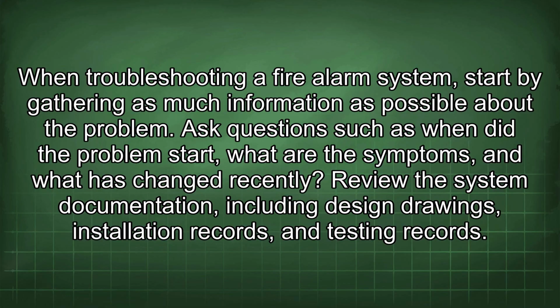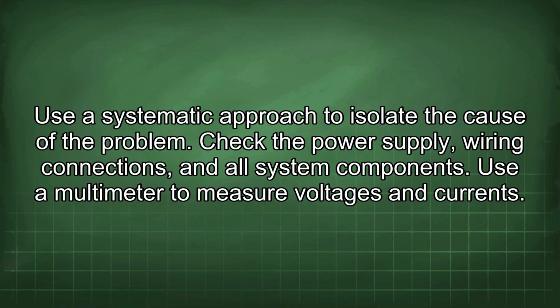When troubleshooting a fire alarm system, start by gathering as much information as possible about the problem. Ask questions such as when did the problem start, what are the symptoms, and what has changed recently. Review the system documentation, including design drawings, installation records, and testing records. Use a systematic approach to isolate the cause of the problem.